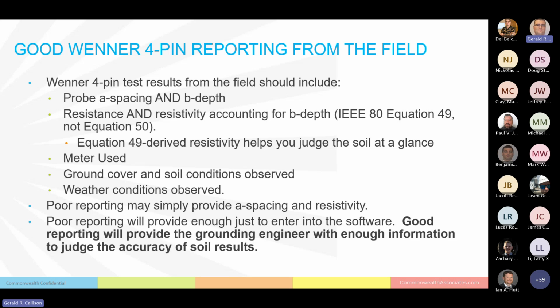Good Wenner 4-pin reporting from the field should include probe A spacing, that horizontal spacing, as well as the probe depth. It should include the resistance and resistivity, accounting for B depth, meaning using equation 49, not equation 50, since it's more accurate at the lower depths where the ground grid is buried. The equation 49 derived resistivity will help you judge the soil at a glance.